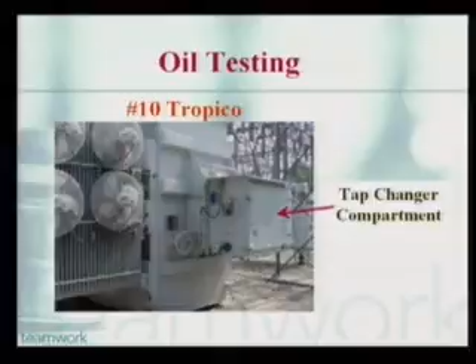Unfortunately, we couldn't take it out of service until after the summer load was over. We did the testing right immediately after the summer. It showed that we have a lot of gases forming inside the transformer, and we followed this recommendation from our vendor saying, basically, take this out of service now before it fails. So this is a preventative measure that we take in the transformer. And what we found there, going back to the transformer, inside the compartment is a load tap changer, and it's normally soaked in oil. And after we empty out the oil, it looks nice and clean.